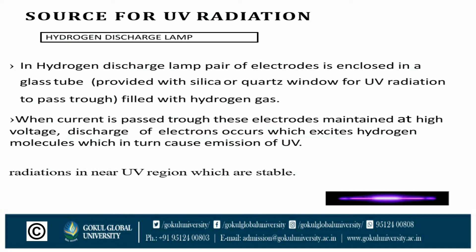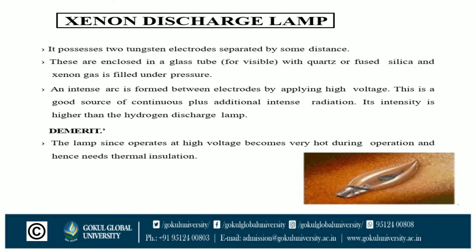It produces radiation in the near UV region which is stable. The xenon discharge lamp possesses two tungsten electrodes separated by some distance. These are enclosed in a glass tube — quartz or fused silica for visible use — and xenon gas is filled under pressure. An intense arc is formed between the electrodes by applying high voltage, making it a good source of continuous, intense radiation.